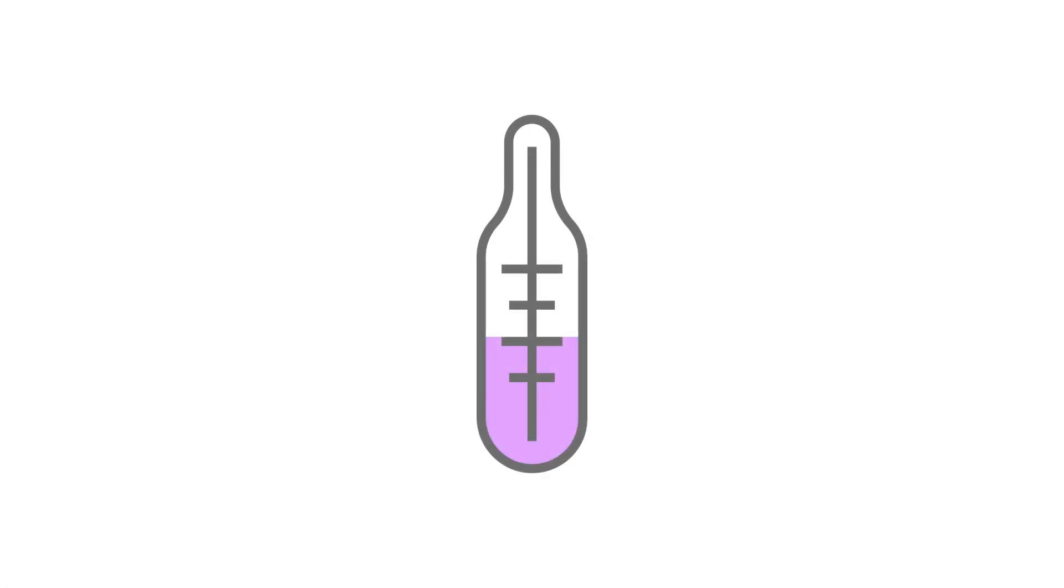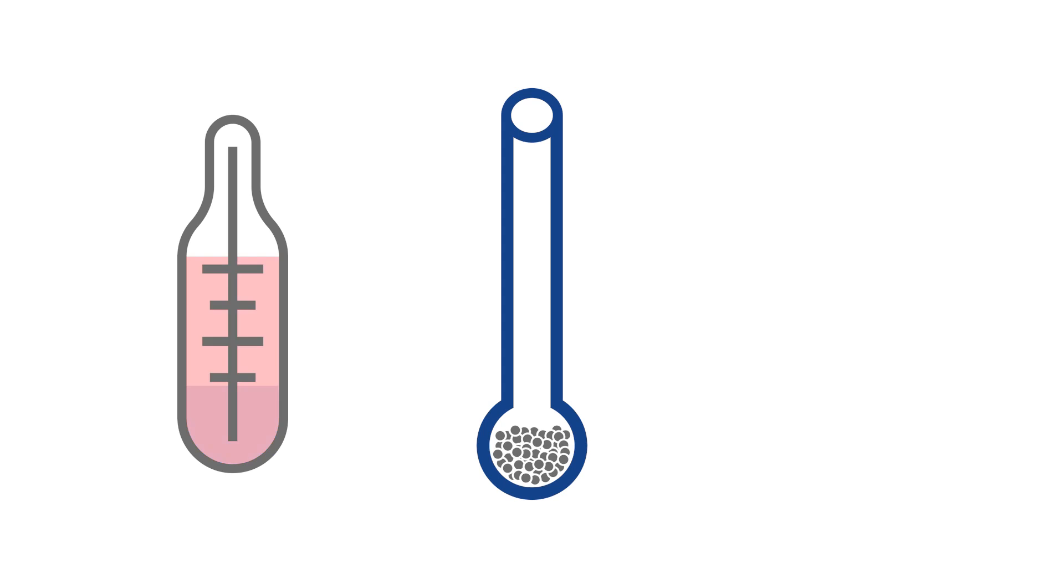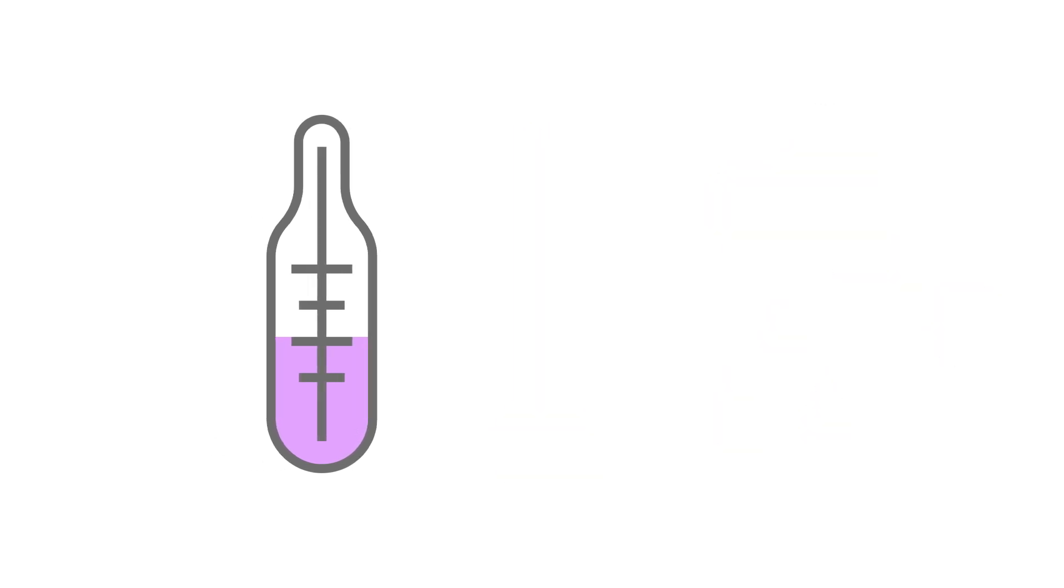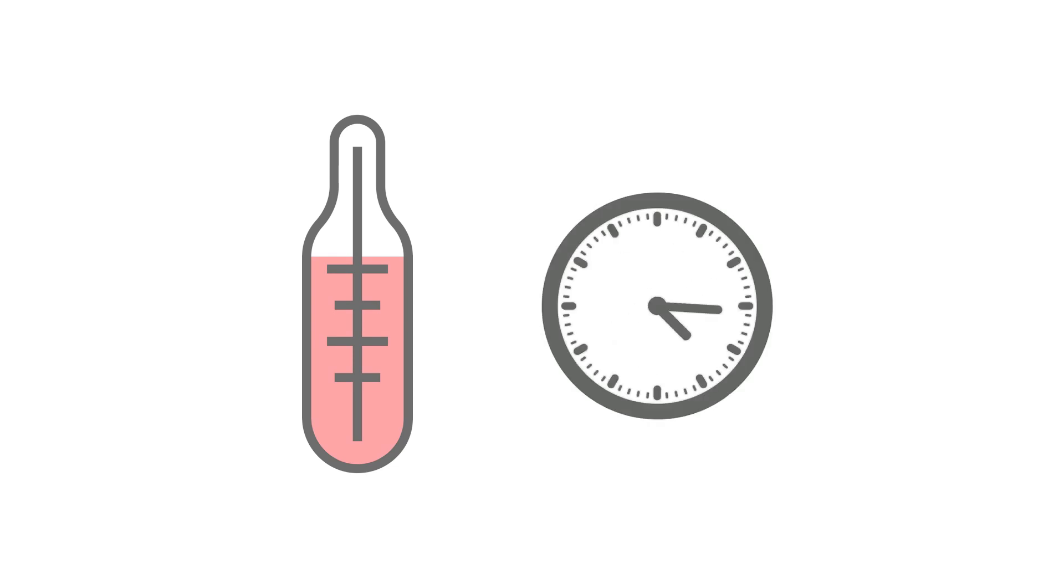Another factor to consider is the temperature. Carefully select the temperature so the surface of the sample is clean and free from any moisture or atmospheric gases without compromising the sample. High temperatures can speed up the degas time and clean the surface faster, but it's not always the correct approach.